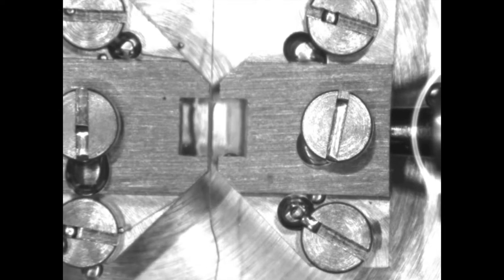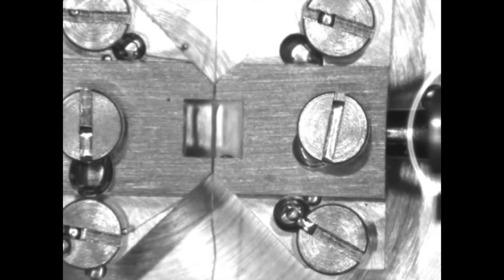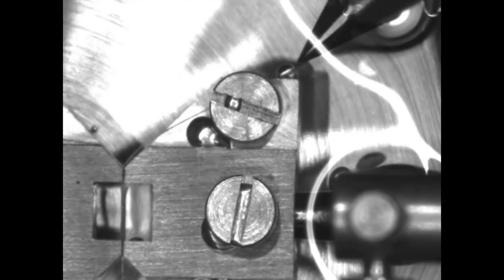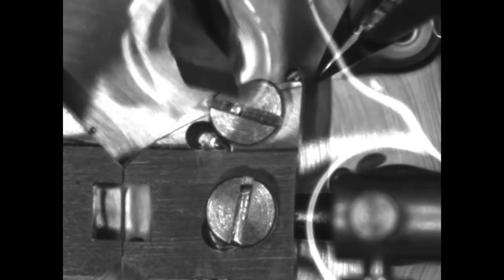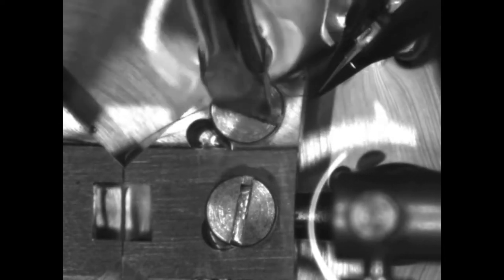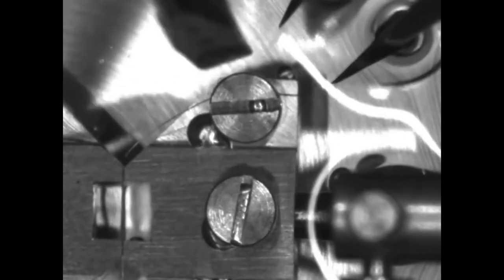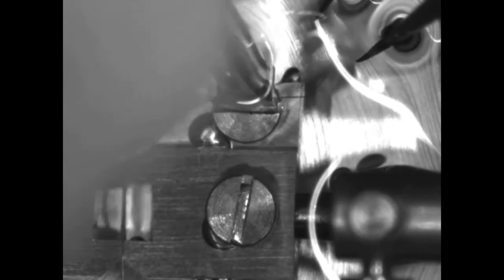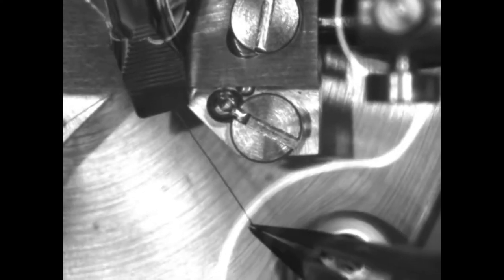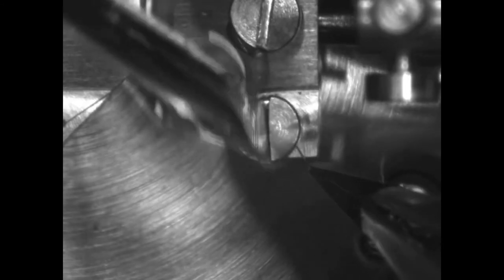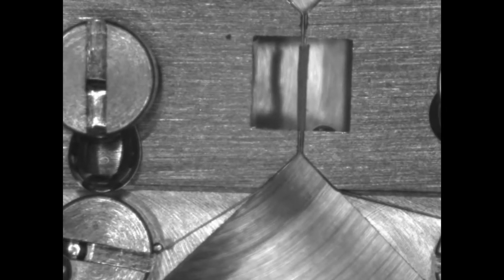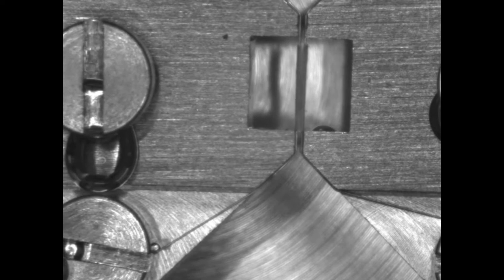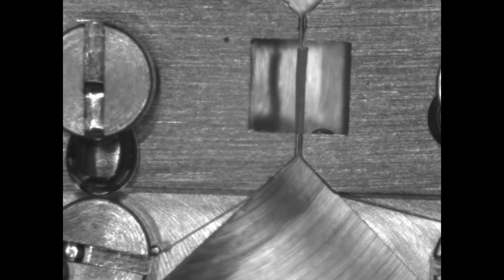Move the jaws together and make sure that the second wire is under the first. Secure one end of the second wire, again in a clockwise manner. Pull and make sure that the second side is tight and secure the second end. You can now slightly open the gap and check that the wires are taut. Before moving back to the interface, move the wires so that they are almost touching side by side.